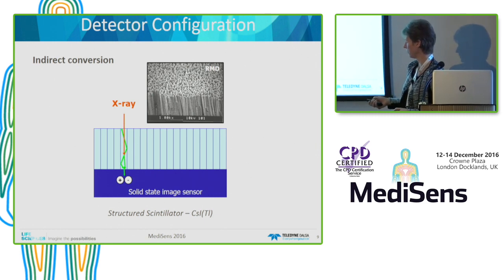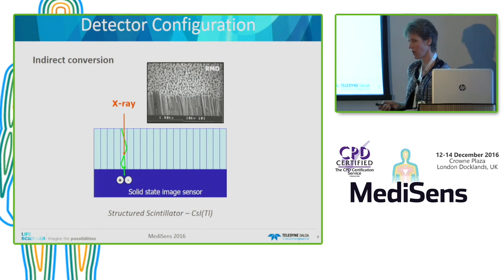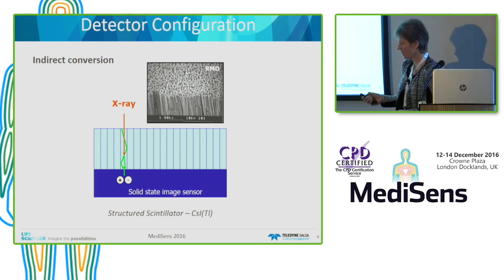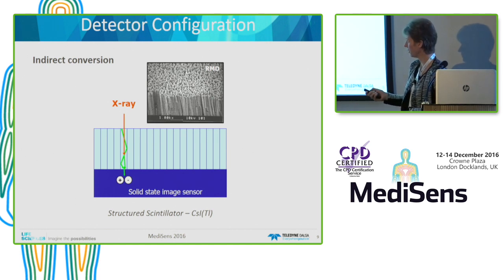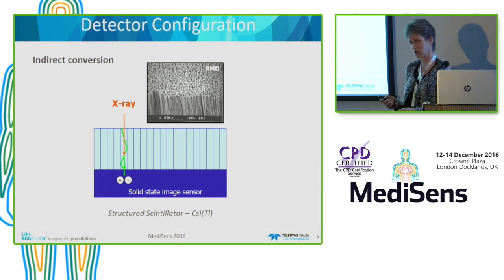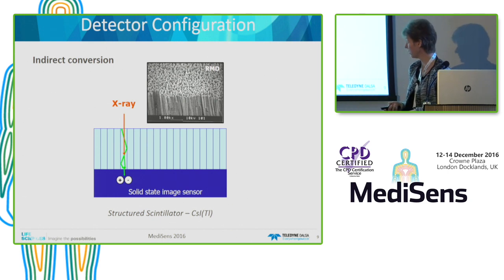For medical imaging, the scintillator material has a needle-like structure, with needles on the order of a few microns, which confines the light into these needles. It's not true that all light is confined — there's still some spreading possible — but it is rather confined compared to other scintillators like Gadox. The thickness of the scintillator has an influence on how much x-ray is absorbed: the thicker the scintillator layer, the better the absorption.